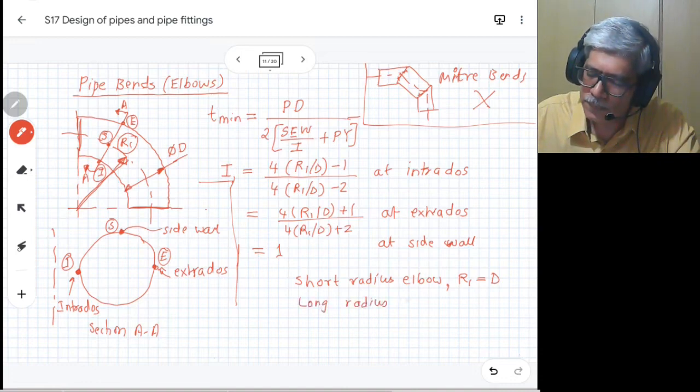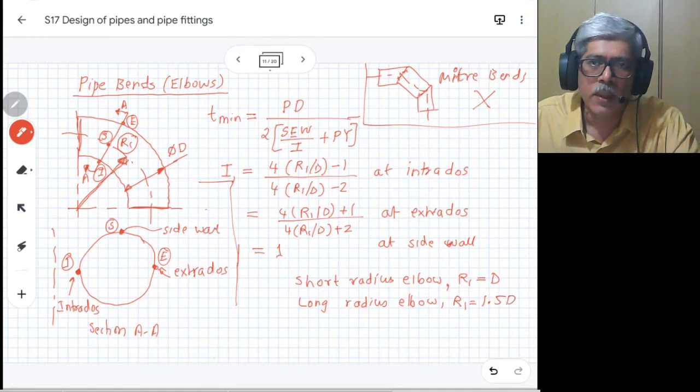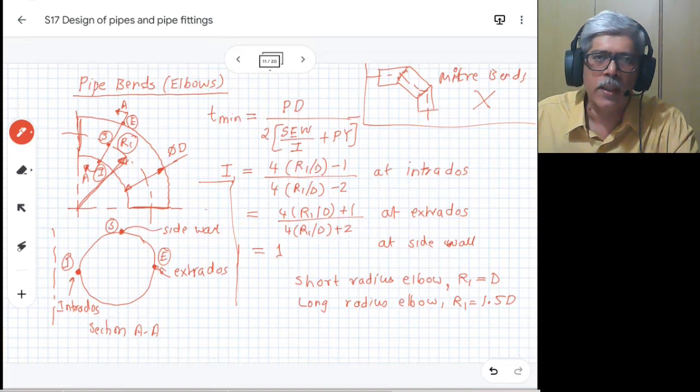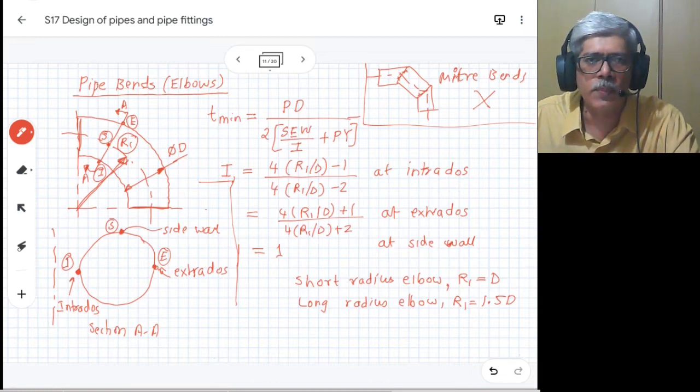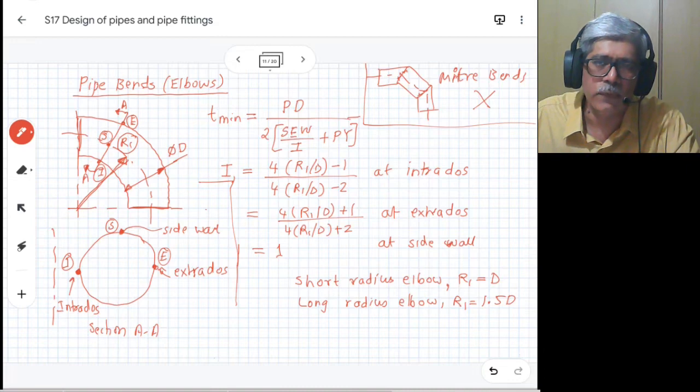In general, the long radius elbow is preferred because it requires lesser thickness, but on the compensating side, you require more space to accommodate that. So if you have space constraint, then only you will go for short radius elbow.